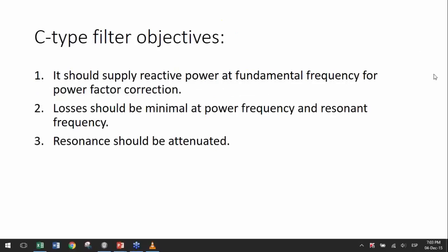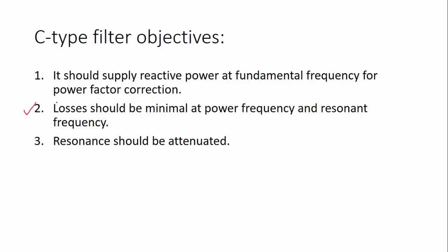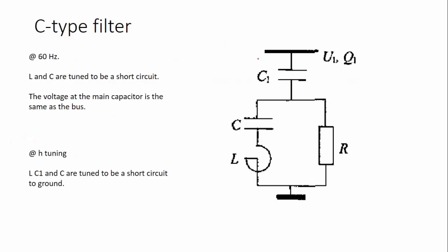So what should be the objective of a filter? A filter should supply reactive power at fundamental frequency for power factor correction, which is what every capacitor and every filter does. Now, this is a plus. Losses should be minimal at power frequency and resonant frequency, or at least near the resonant frequency, which is a trouble that the second and third order filters have. The losses tend to be high at low frequencies. So in order to save money and reduce cost, losses should be minimal. And besides, resonance should be attenuated. Otherwise, a notch filter would work, but I don't think the notch filter is a solution. So this is a very important factor in C-type filters. Some very clever fellows came up with this solution. And this is a C-type filter.